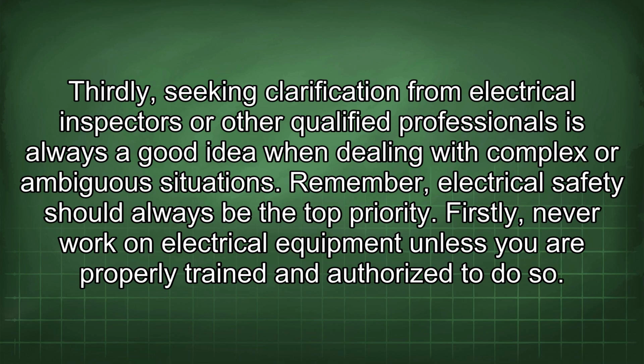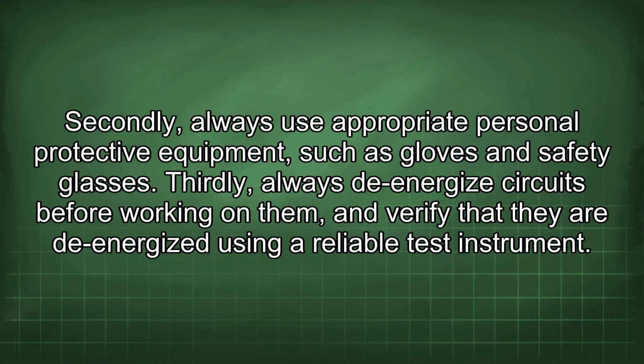Remember, electrical safety should always be the top priority. Firstly, never work on electrical equipment unless you are properly trained and authorized to do so. Secondly, always use appropriate personal protective equipment, such as gloves and safety glasses. Thirdly, always de-energize circuits before working on them, and verify that they are de-energized using a reliable test instrument.